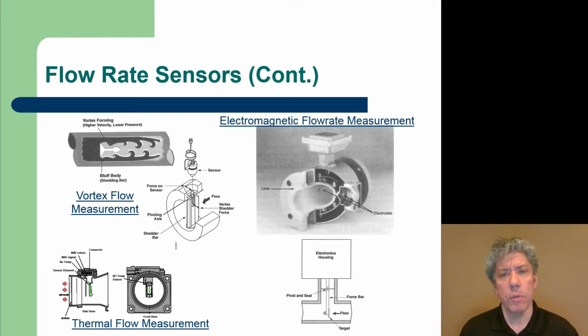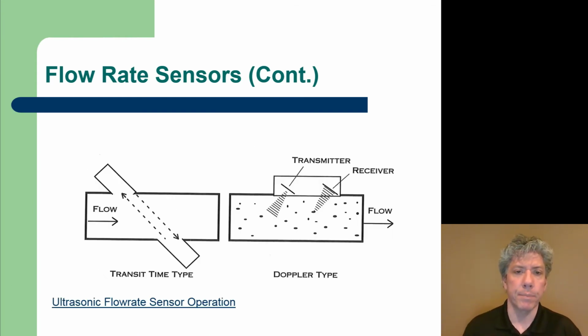Another way is with something called a flow target in the lower right-hand image. You've probably done something like this. If you ever stuck your hand out of your car window as you're moving, you notice that at higher velocities, the air pushes your hand back farther. That's exactly how this works. You see the target down there is in the flow stream, and the flow pushes on this target, and the target is essentially spring-loaded, so that the higher the flow rate, the harder the flow pushes against the target, deflecting the target farther and farther against the spring, and by measuring that deflection, you can infer the flow rate.